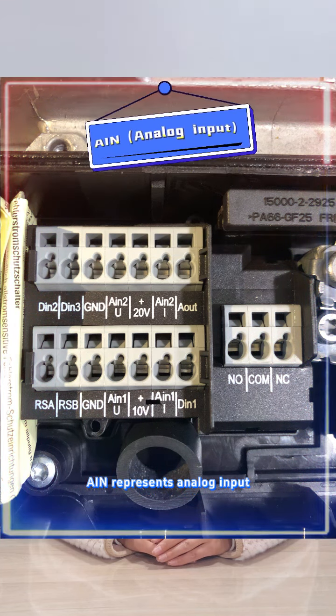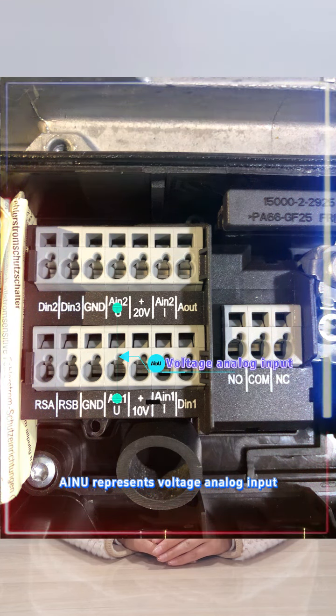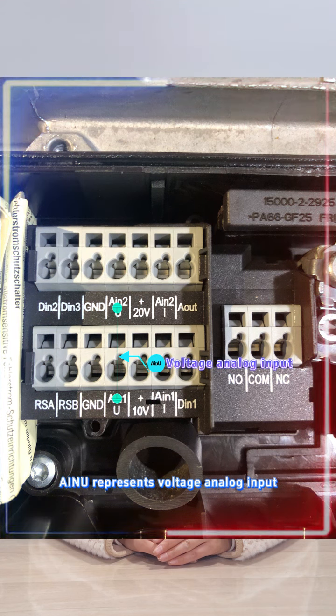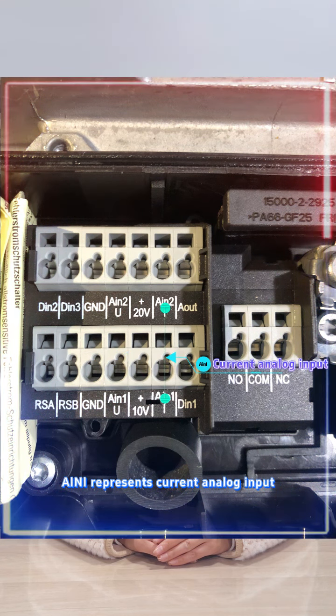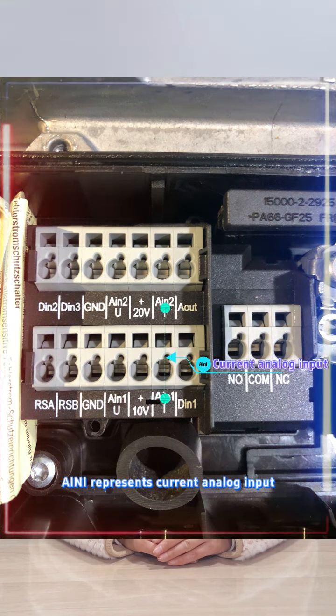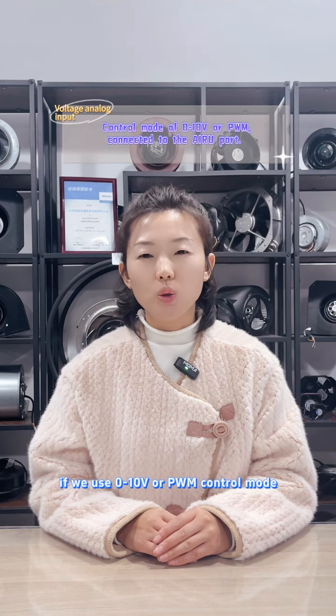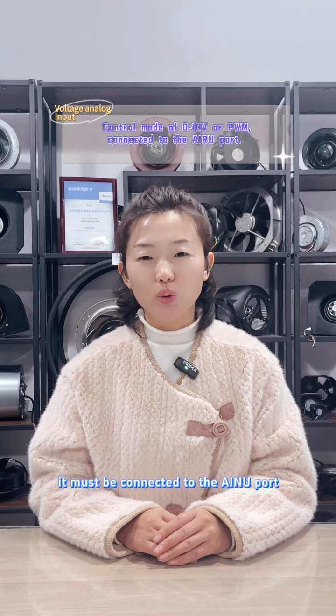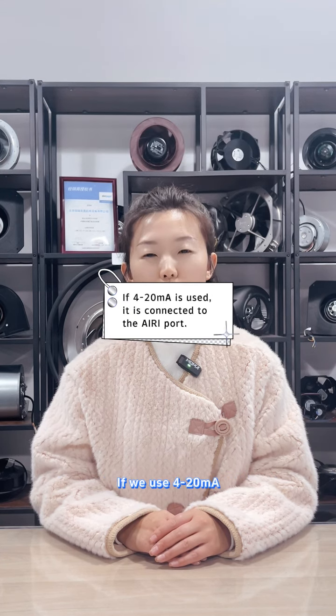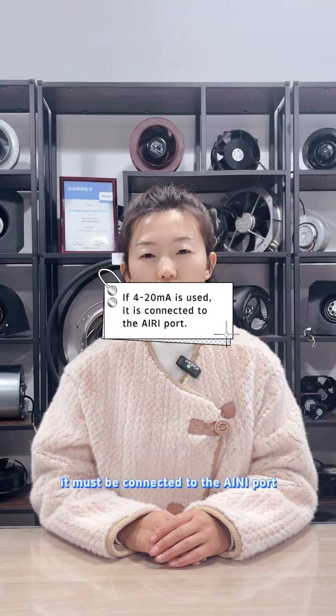AIN represents analog input. AINU represents voltage analog input. AINI represents current analog input. If we use 0-10 volt or PWM control mode, it must be connected to the AINU port. If we use 4-20 mA, it must be connected to the AINI port.